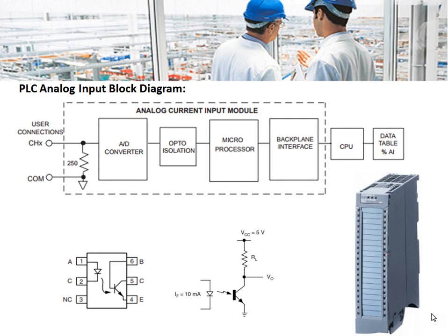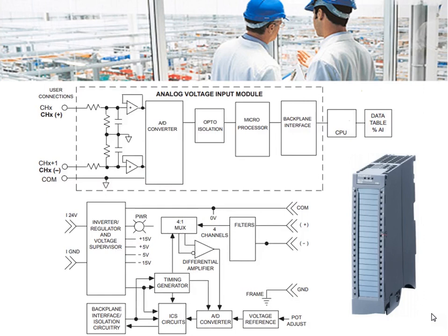A typical opto-transistor and diode are used for isolation purposes. This is the analog voltage input module, and it is of differential type. Differential type input is preferred over single-ended because it is less sensitive to noise and ground currents. The signal is fed to the ADC, and through opto-isolation it is fed to the microprocessor and then to the CPU of the PLC.